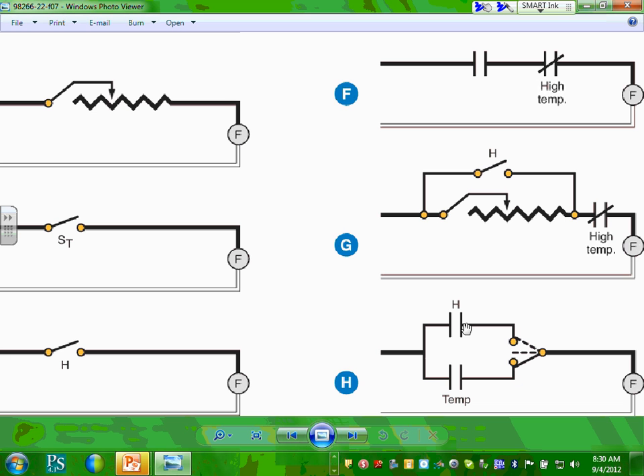You also said in the notes that the heat lamp cannot be on without the fan being on. Is there a relay? Yes, there's a control inside. The heater cannot be on without the fan being on, because if you run the heater without moving air, what's going to happen to your fixture? You could burn it. So there's an interlock inside the fixture. In reality you turn the heater and the fan on together, because you want to heat and push the air down. When you turn the fan on, the heater will not go on, and that's all inside the control of that fixture. Good point. Any questions, guys, about these?